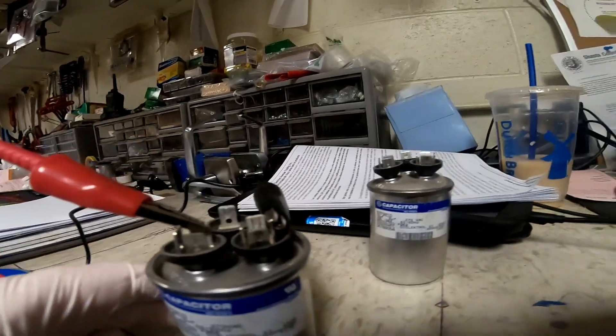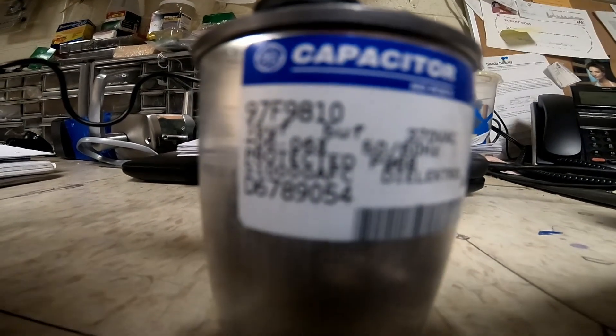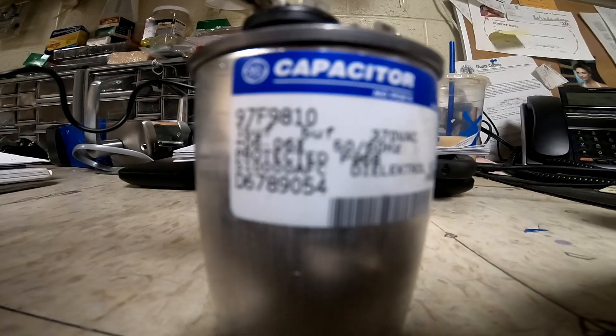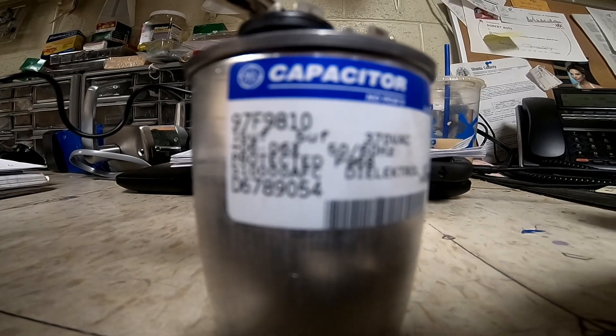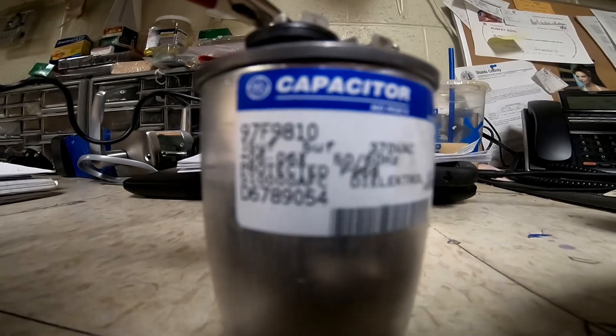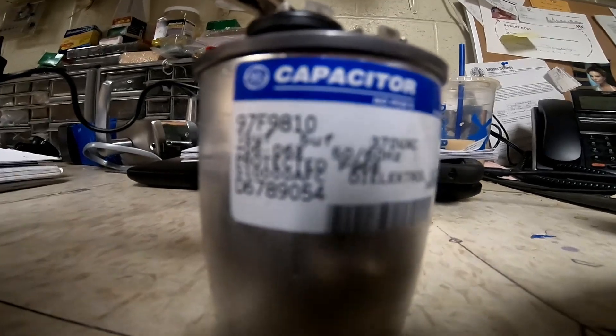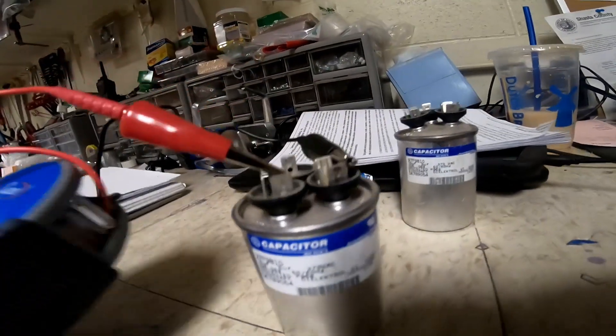This one's got a flat top on it, and our rating here is, not sure if you can see that, but it's a 15 µF and 5 µF, plus or minus 6 percent. And we can test to see if it's good.